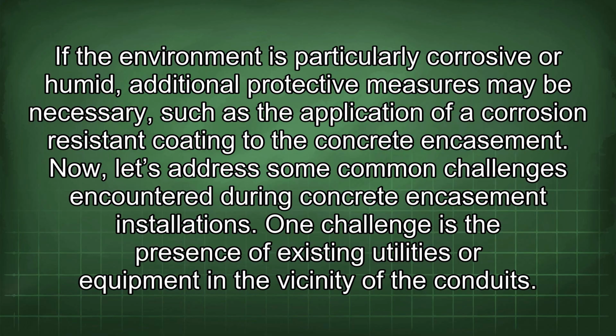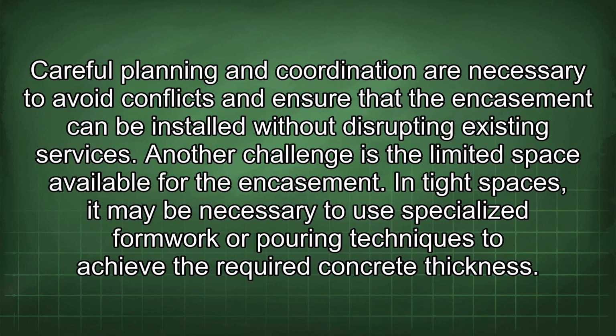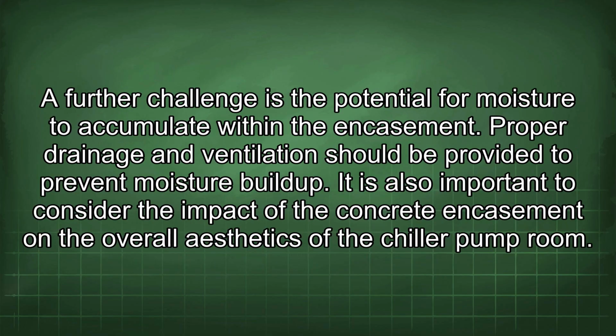Now let's address some common challenges encountered during concrete encasement installations. One challenge is the presence of existing utilities or equipment in the vicinity of the conduits. Careful planning and coordination are necessary to avoid conflicts and ensure that the encasement can be installed without disrupting existing services. Another challenge is the limited space available for the encasement. In tight spaces, it may be necessary to use specialized formwork or pouring techniques to achieve the required concrete thickness. A further challenge is the potential for moisture to accumulate within the encasement. Proper drainage and ventilation should be provided to prevent moisture buildup.